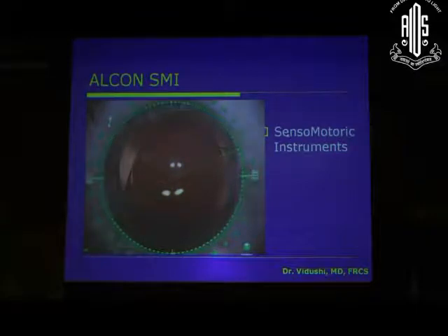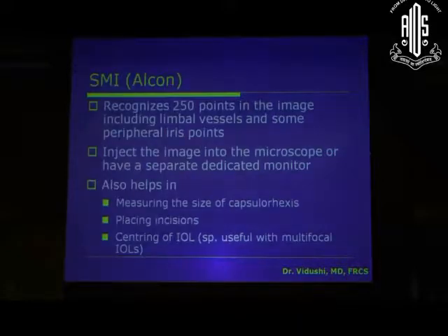Then you have the SMI, which is manufactured by Sensomotoric Instruments, now bought over by Alcon. This is also commercially available now in India. It gives you this kind of transparency within the microscope, and you can align your toric IOL according to this. It is based on limbal and iris registration, and it recognizes 250 points in the image. You can either put this image into the microscope and look through that grid while you're doing the surgery, or you can have a separate dedicated monitor which will show you the grid and your toric IOL alignment.